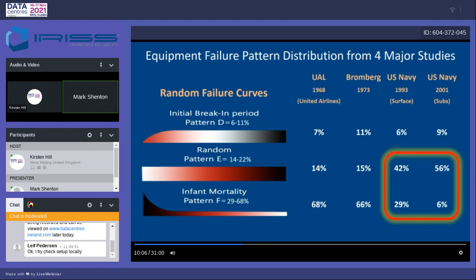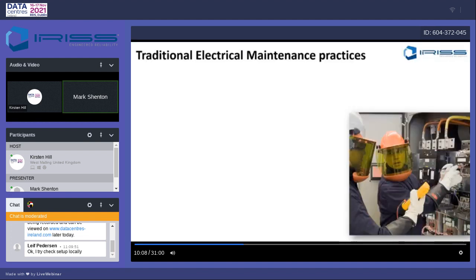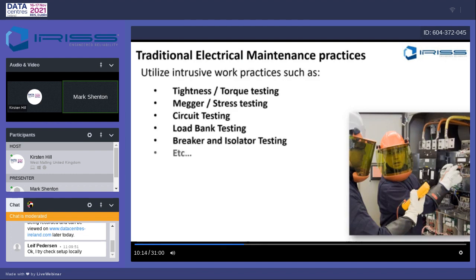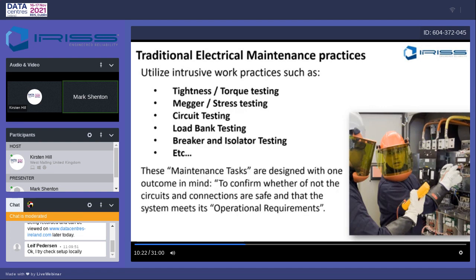Traditional electrical maintenance practices utilize intrusive work practices — tightness testing, megger stress testing, circuit testing, load banks, etc. These are all done, but why do we do the maintenance? We want to confirm that the circuits and connections are safe, and that it's meeting its operational requirements. So primarily we do that maintenance and testing to prove that to ourselves, and to show legislative bodies that we're taking care of it from a safety standpoint.